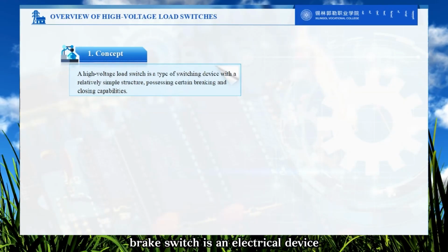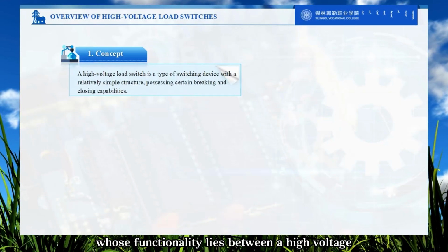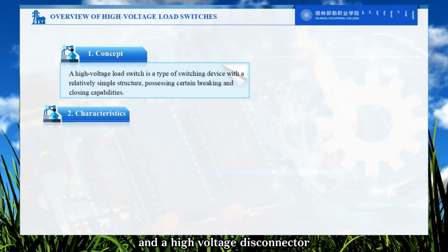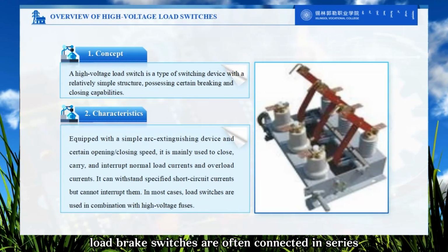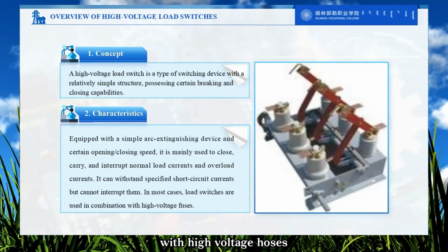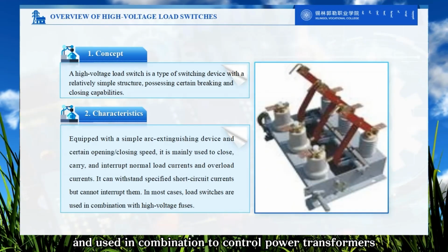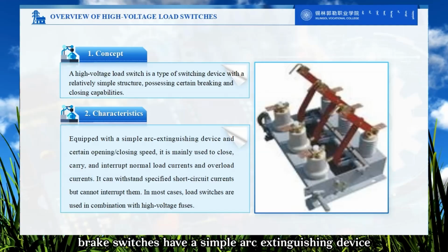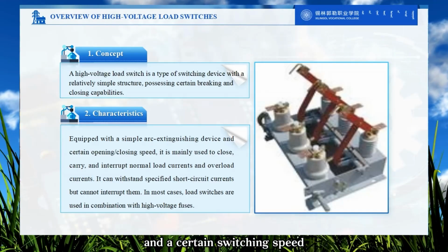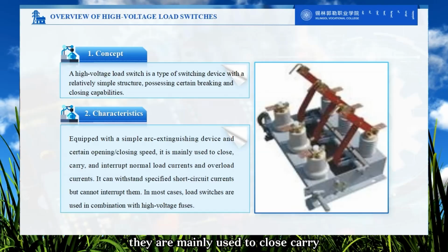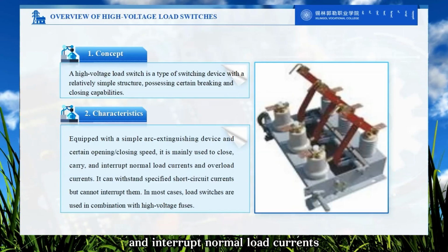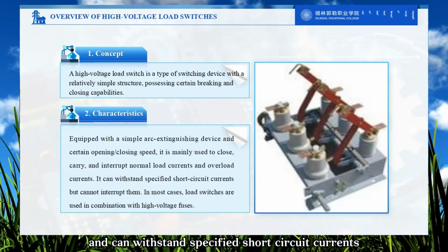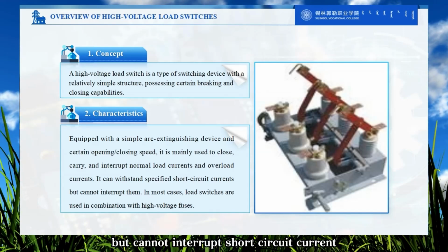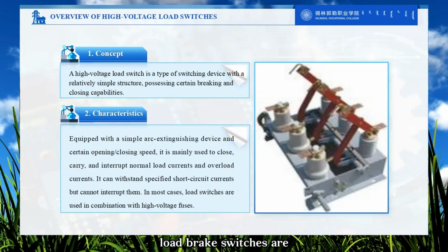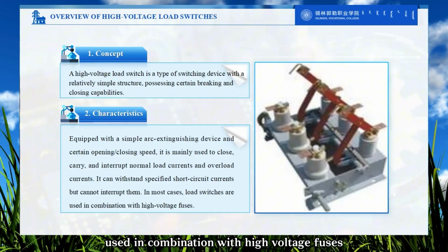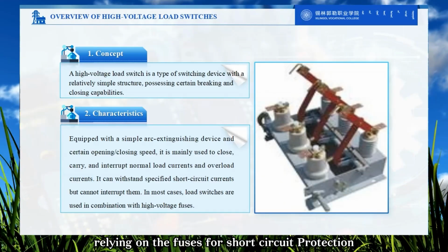A high-voltage load break switch is an electrical device whose functionality lies between a high-voltage circuit breaker and a high-voltage disconnector. High-voltage load break switches are often connected in series with high-voltage fuses and used in combination to control power transformers. High-voltage load break switches have a simple arc extinguishing device and a certain switching speed. They are mainly used to close, carry, and interrupt normal load currents and overload currents, and can withstand specified short-circuit currents, but cannot interrupt short-circuit current. In most cases, load break switches are used in combination with high-voltage fuses, relying on the fuses for short-circuit protection.